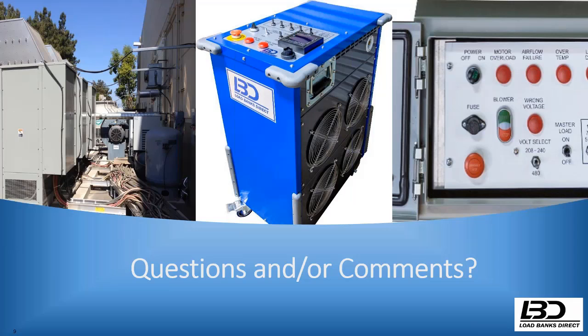That should cover the medium voltage application for these. Obviously with those, it requires a much larger trailer than just a load bank by itself, due to the size of the transformer. Most of the transformers we pair with our load banks, for medium voltage, are usually in the 2 to 3 megawatt range. So the transformer is just as big, if not bigger, than the load bank, and definitely weighs more. Just in terms of the installed footprint, you're looking at a much larger trailer with a much higher GVW rating as well.